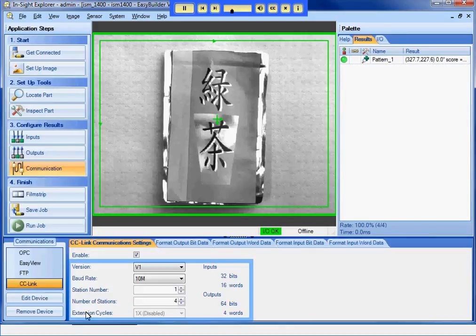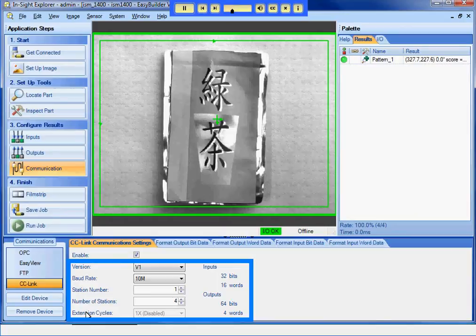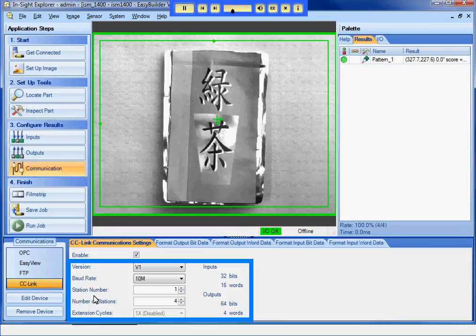I will set up In-Sight to communicate using version 1 of CC-Link. In-Sight is capable of version 2 as well. I will set the station number to 1 and the number of stations to 4. I will make sure that these values match the settings on the PLC.